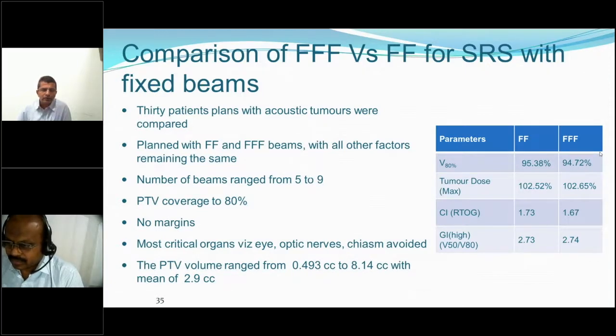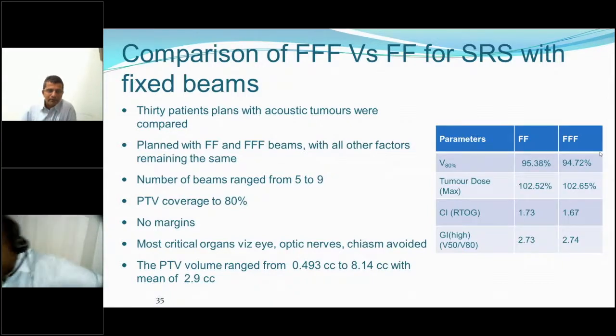Sir, one more question I have here. There are many more questions, but probably some of the interesting questions they are asking now is, how can we measure the output factor for the tertiary collimator for small fields without using a reference chamber? See, if you're measuring on a LINAC, I would suggest you have to use a reference chamber. For output, it is not a major issue. Like when I do the output measurement, I don't use a reference chamber, right? Output measurement I don't use, and in the same condition I do the output factor also. So I actually don't use a reference chamber.